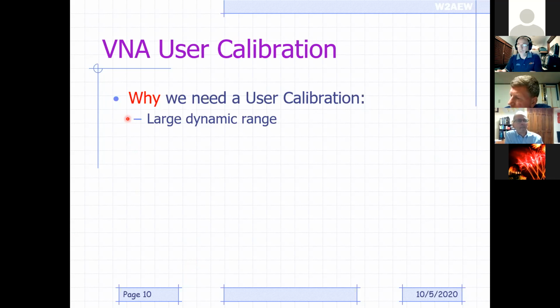So in order to do that, any tiny little mismatches or things that we do in how we hook something up can affect the measurement. So we want to calibrate much of that out. That's one of the reasons why we do a user cal. Another one is that we're measuring phase. Remember what I said about phase? Phase is really just a measurement of delay. So if I've got to take a piece of coax to hook up from my NanoVNA to my device, there's going to be some delay associated with that. So if we just measured it, we're going to measure that delay in addition to whatever alteration in phase my device is going to do.